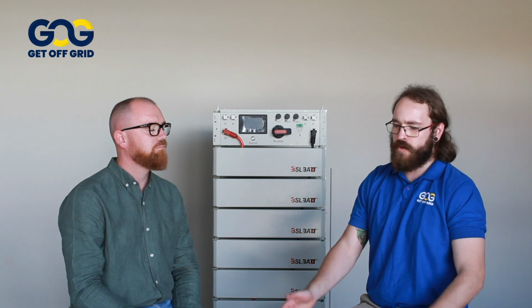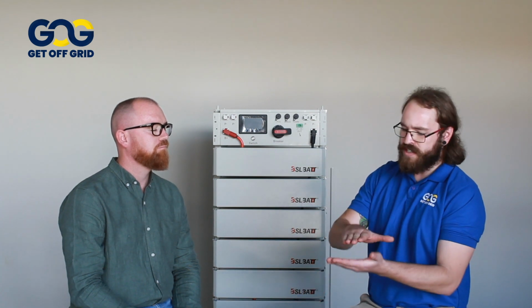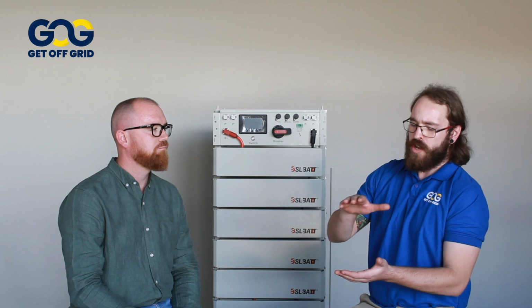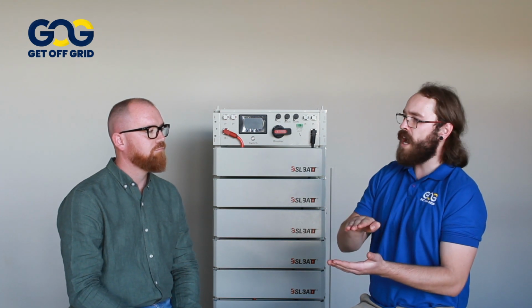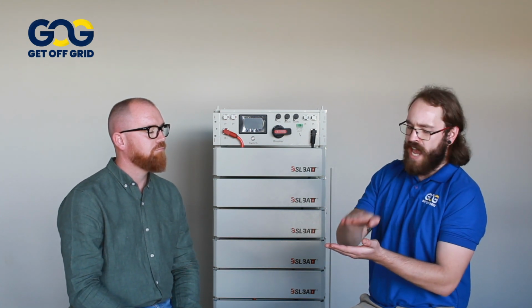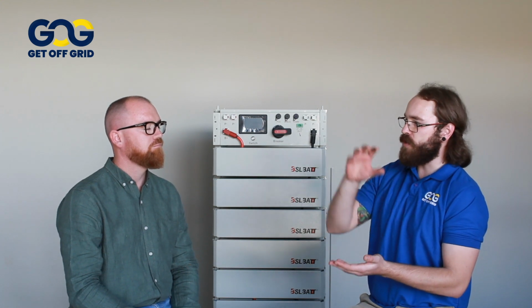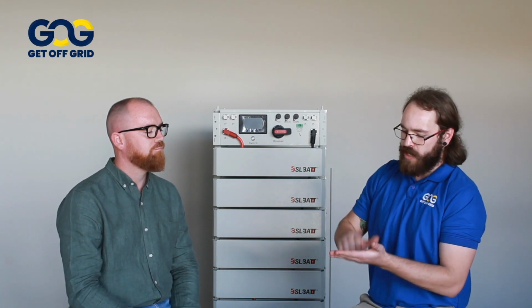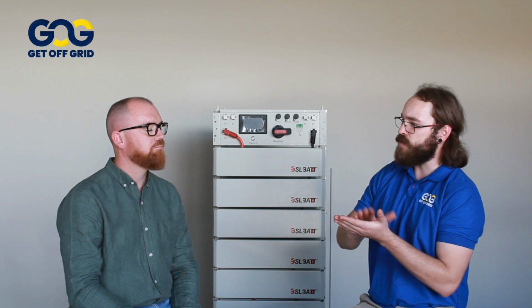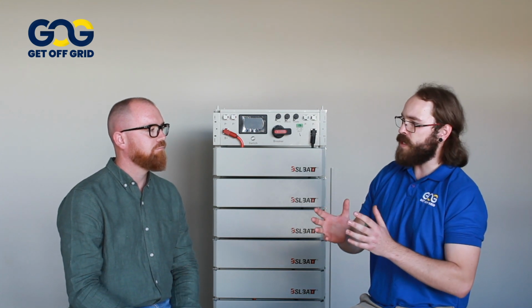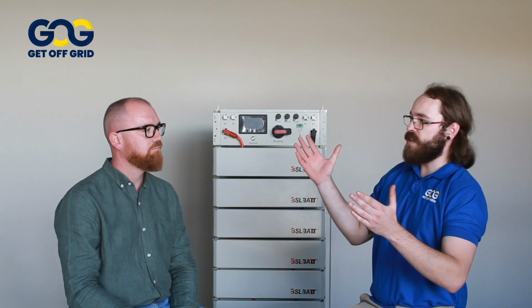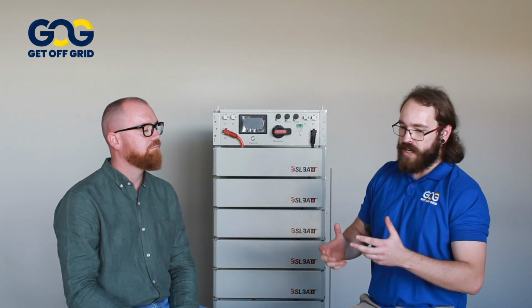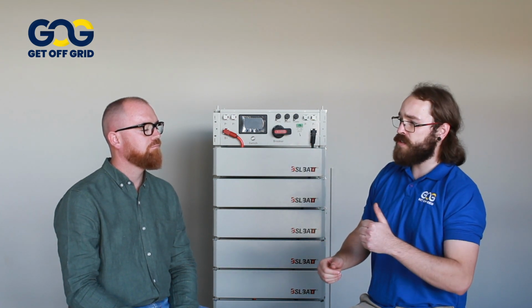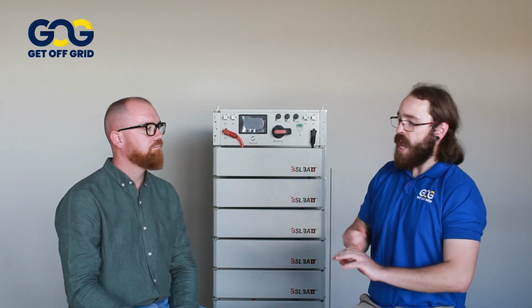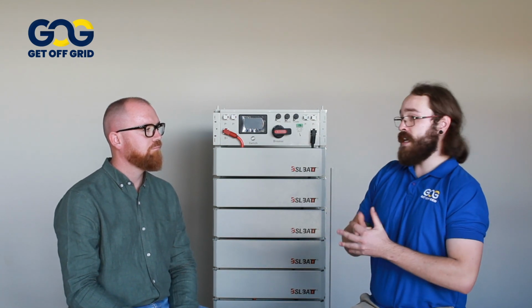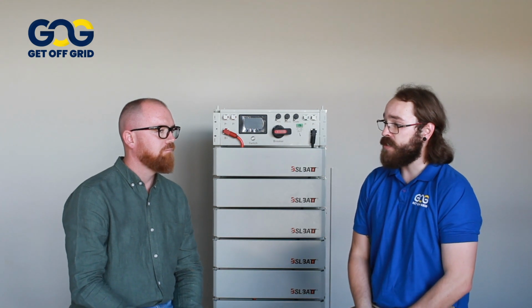The batteries come in a number of different configurations. It's essentially a stackable configuration, so whatever your designated or required standard voltages are, you can stack the modules to achieve a certain requirement. For example, if you have a stack of 8, 9, or 10 batteries, you will be operating between 450 and 680 volts, which is more than enough to be compatible with a lot of the latest units and any other high voltage requirements coming out of the market.